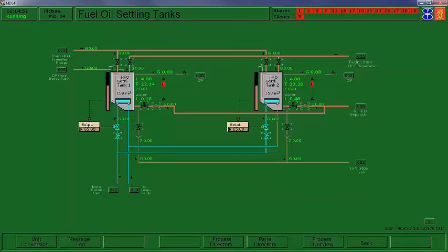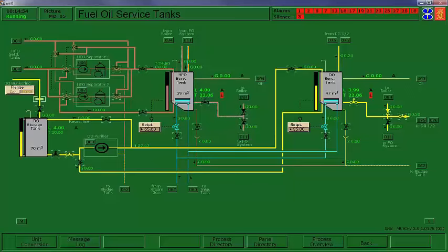All right, from the settlers, we will now go to our service tanks, and we'll put the steam on both the heavy and the diesel. Again, the set point here is 65, though I see people running this up to about 80. And again, think about how much vapor you're producing. They do it because some of the modern fuels put a lot of load on your fuel oil heaters for the main fuel system. All right, so we've got that.